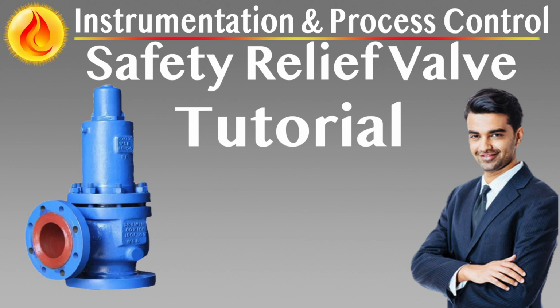Pilot-operated relief valves: use in clean services when the inlet pressure drop exceeds 3% of the set pressure. Superior leak tightness is required due to soft seat design. High back pressure, 50 to 70% of set pressure, must be tolerated. Higher set pressure and compact size are needed for large capacity relief. The margin between system operating pressure and set pressure is less than 10%.